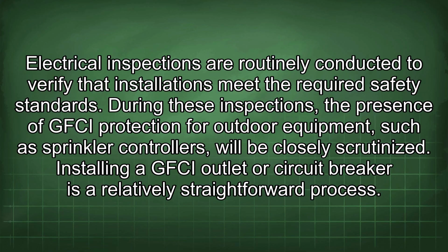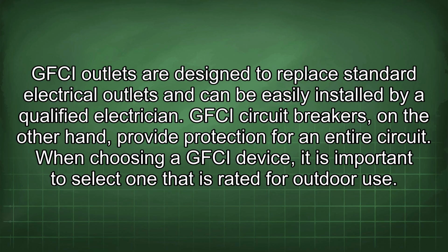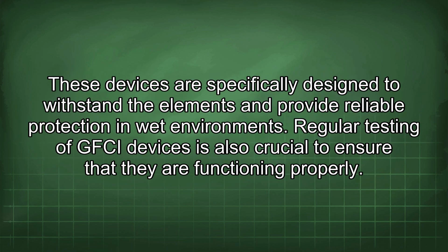Installing a GFCI outlet or circuit breaker is a relatively straightforward process. GFCI outlets are designed to replace standard electrical outlets and can be easily installed by a qualified electrician. GFCI circuit breakers, on the other hand, provide protection for an entire circuit. When choosing a GFCI device, it is important to select one that is rated for outdoor use. These devices are specifically designed to withstand the elements and provide reliable protection in wet environments.